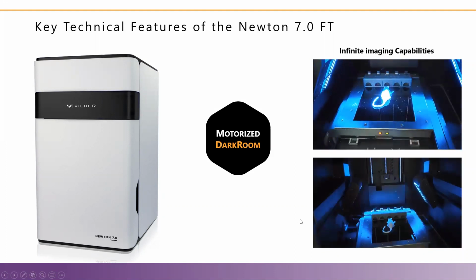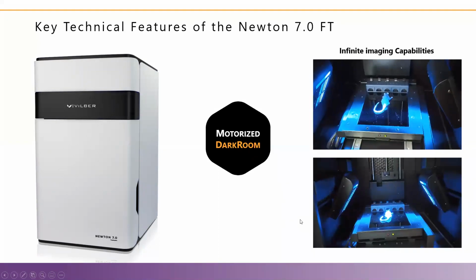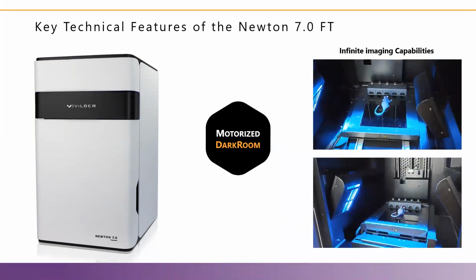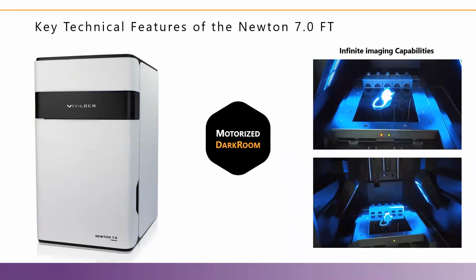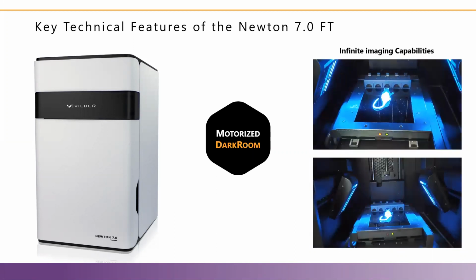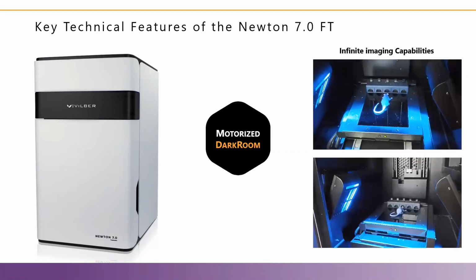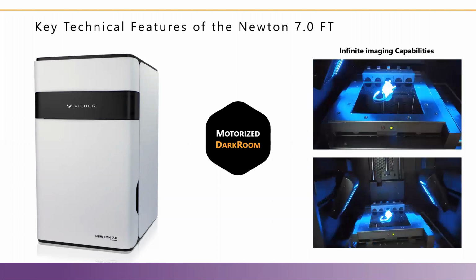Now the excitation light panels are also motorized in the x-axis, shown here on the bottom, and this is to provide a unique scanning technique so that the excitation light is uniform all over the sample surface. And this really provides a more accurate fluorescence quantification.